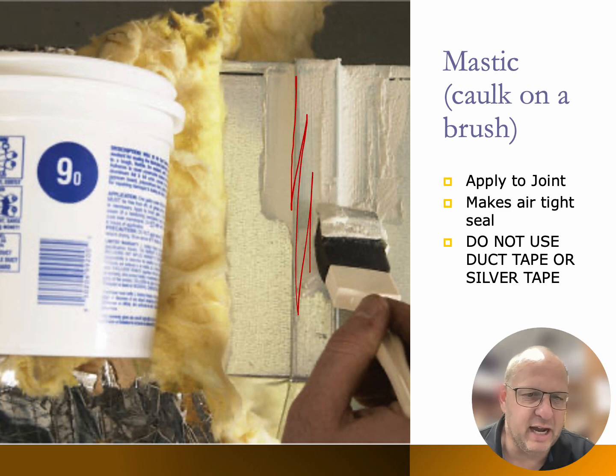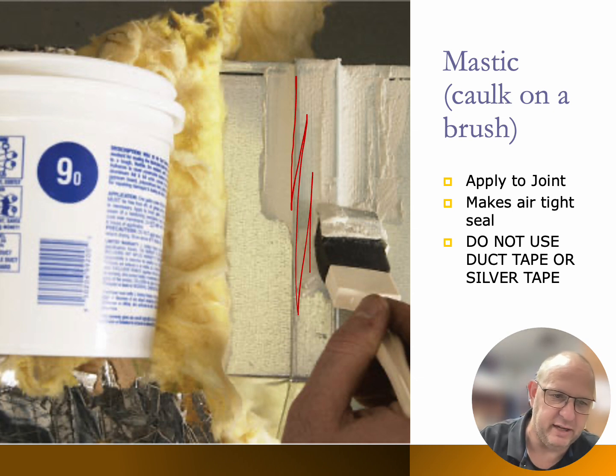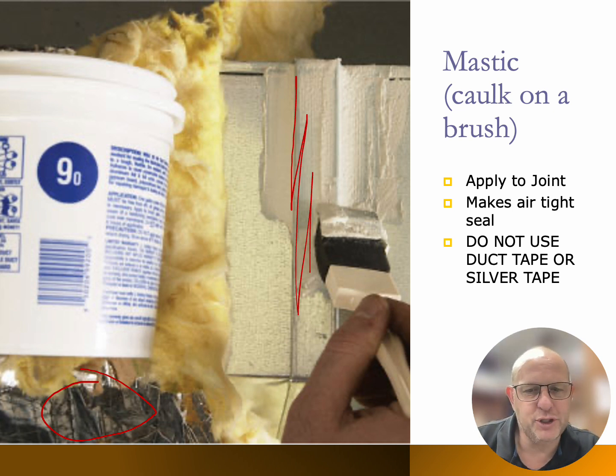On the left-hand side, you can see the insulation that's on there. After we got done putting that mastic type of material, that sealant type of material on that ductwork, we would go ahead and insulate it and then tape it. Tape the insulation, not the ductwork. Now that insulation that you're seeing there, right down in here, you can see it. It is foil back. Foil back insulation is great for a moisture barrier between the ductwork and the air that's on the outside of it.